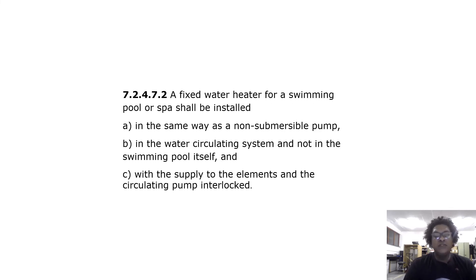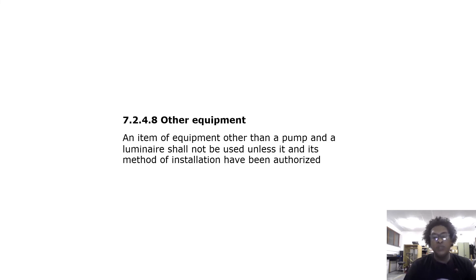A fixed water heater for a swimming pool or spa shall be installed in the same way as a non-submersible pump — in the water circulating system and not in the swimming pool itself — with the supply to the elements and the circulating pump interlocked. An item of equipment other than a pump or luminaire shall not be used unless its method of installation has been authorized.